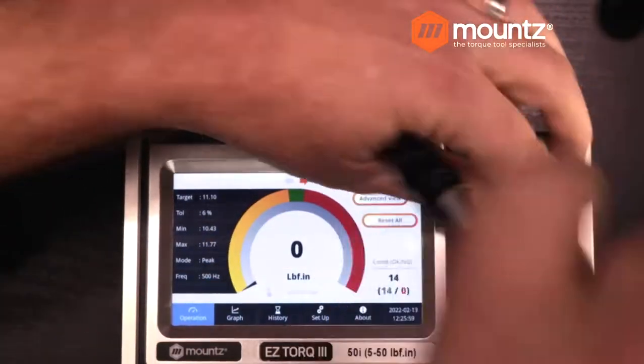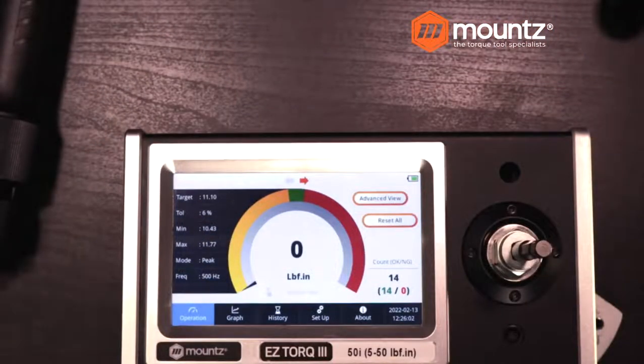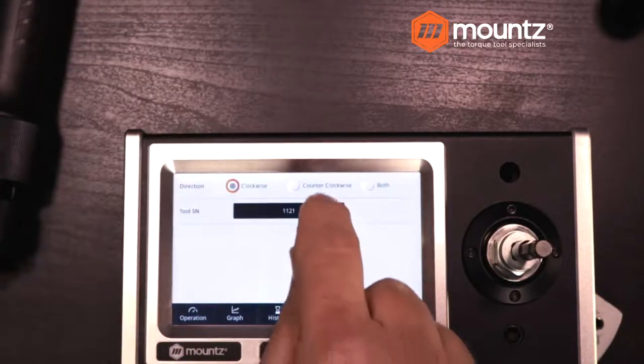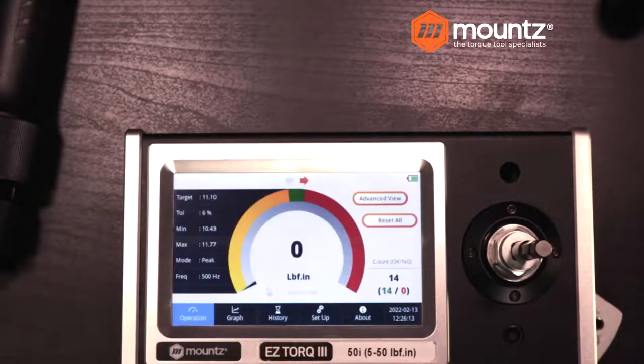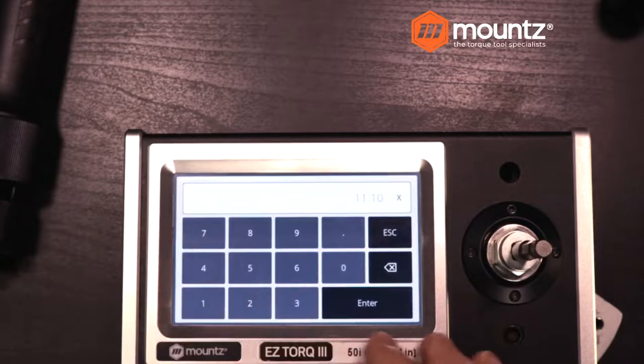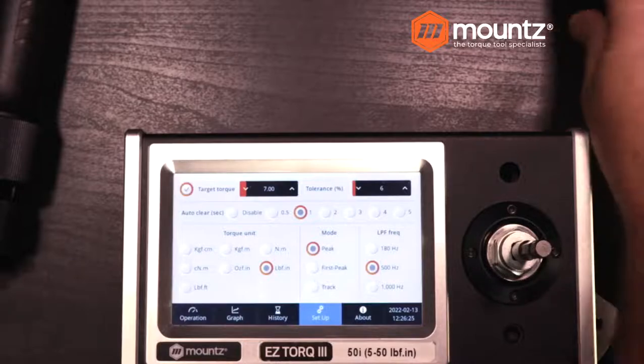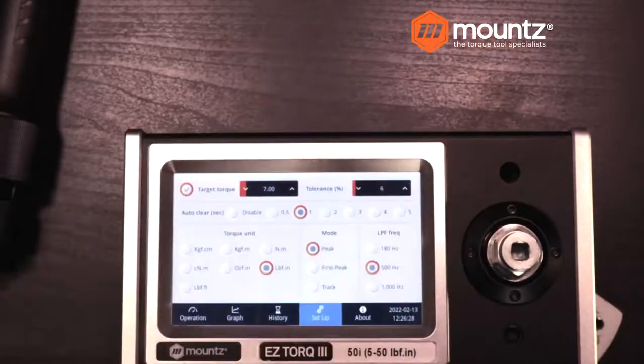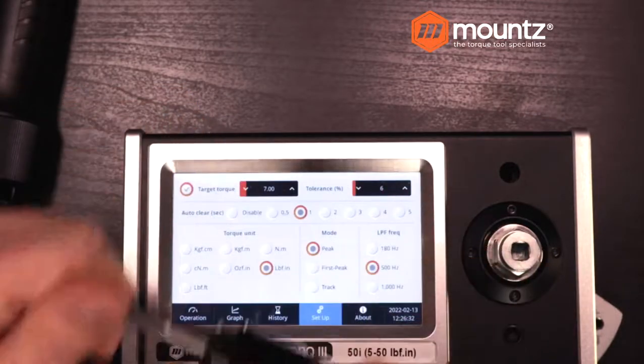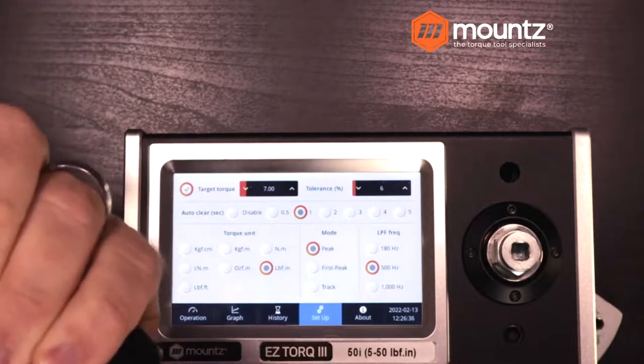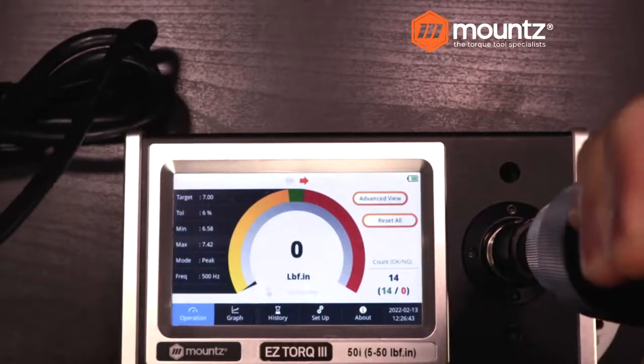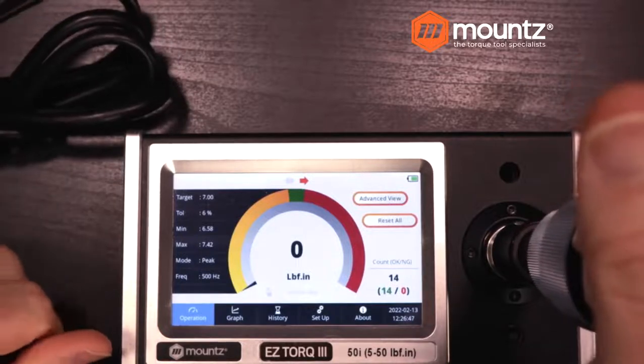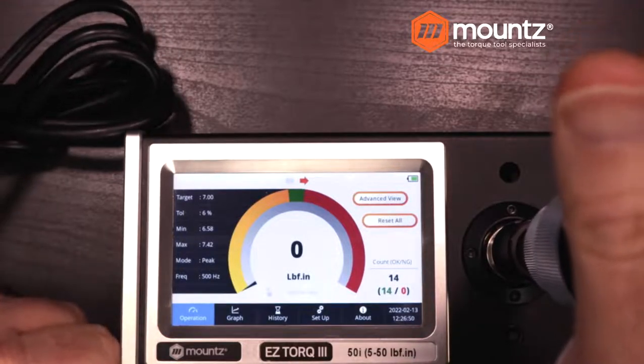Now we can go back to where our serial number is and clear that, then set up our testing for our power tool. We can set our target torque to seven inch pounds, which is where this tool is set. We'll use a rundown adapter or joint simulator to help with the actual rundowns. Again, we want to allow the tool to be used a few times before we actually do our testing.